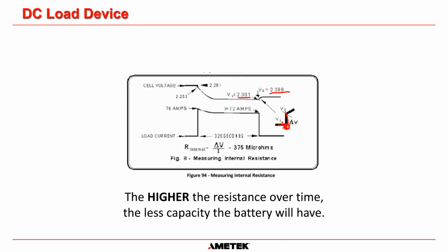Okay, and what they've done is they know the difference between that is 0.027. So they put 0.027 on the top there, and then they divide that by the current, which is 72 amps. And if you do the math, 0.027 divided by 72 amps is equal to 375 microohms. So that is how they work out the internal resistance of a valve regulated battery. And it must be noted that the higher the resistance over time, then therefore the less capacity the battery will have.